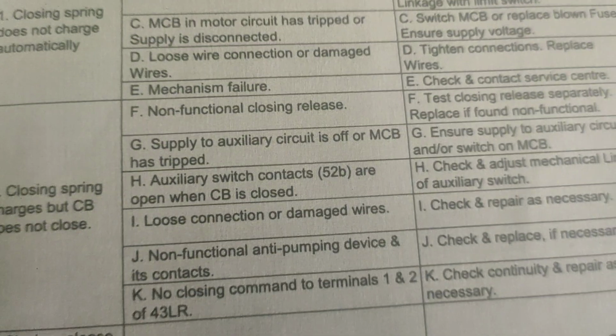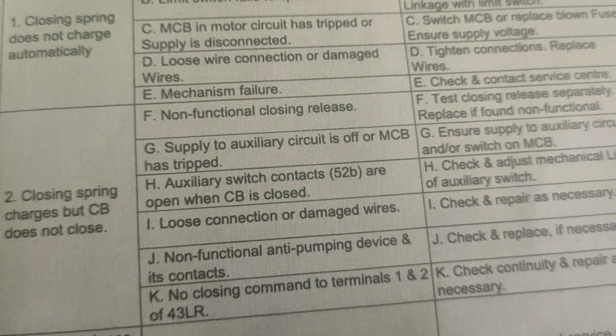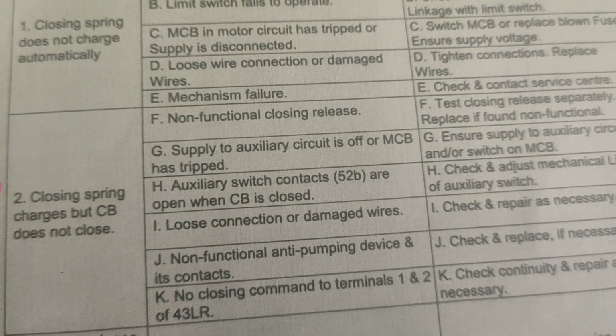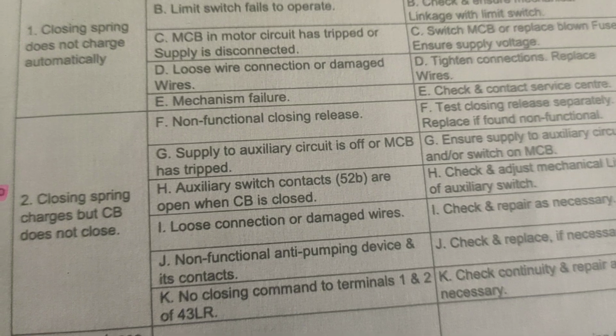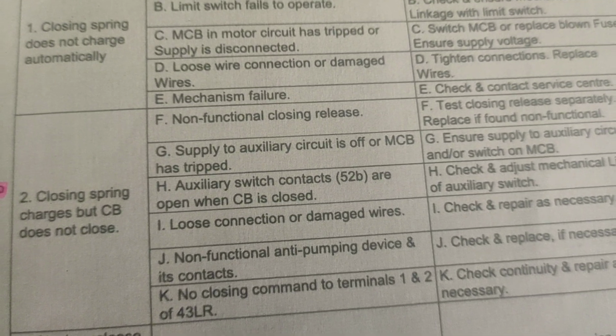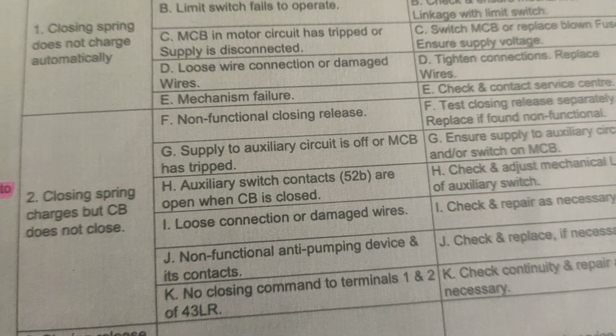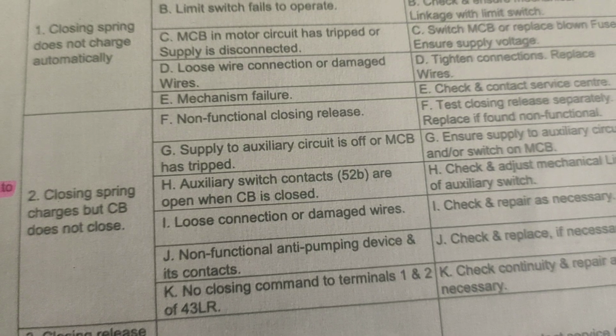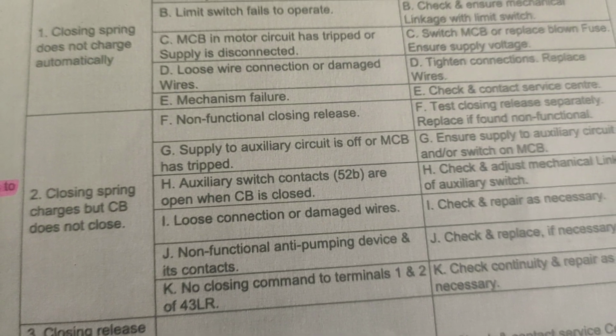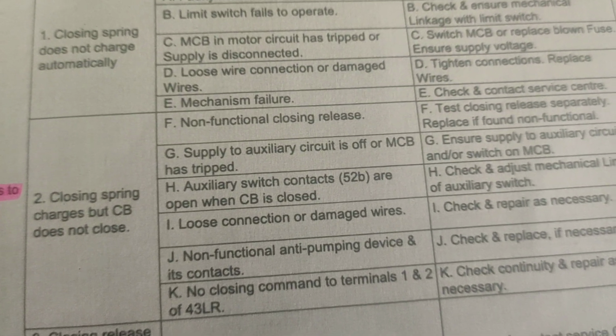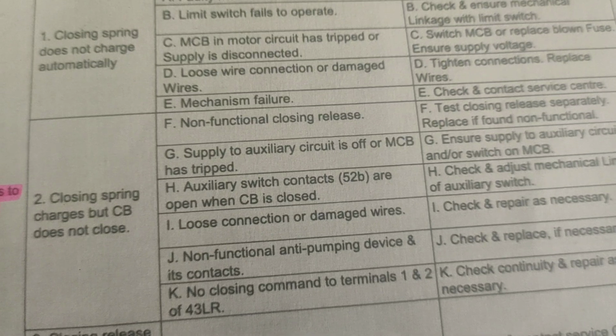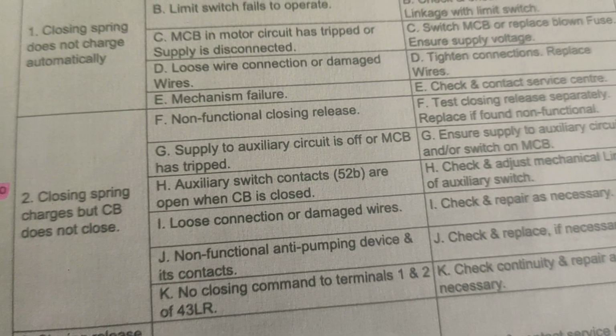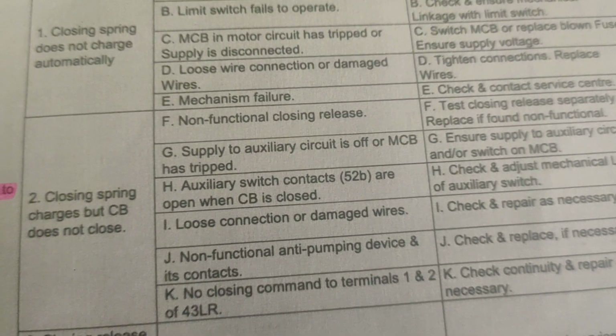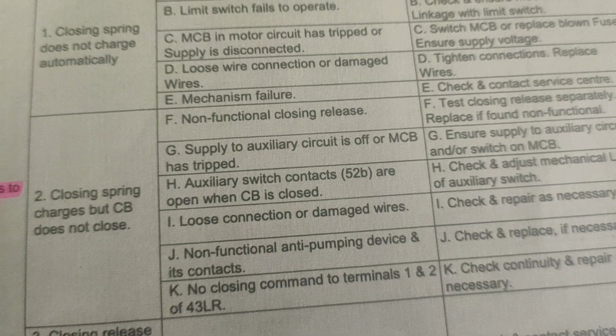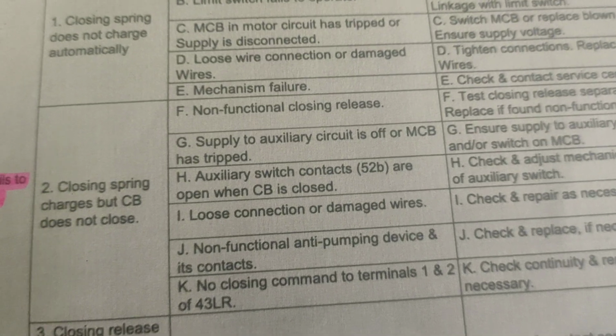Suppose you are trying to close the circuit breaker, but the 52A of the auxiliary contact is in open condition. Then you cannot close the circuit breaker, because it also depends on the auxiliary switch functions. If the 52A is closed, the closing path will be completed. If the closing path is completed, you operate the TNC switch in the closed direction.